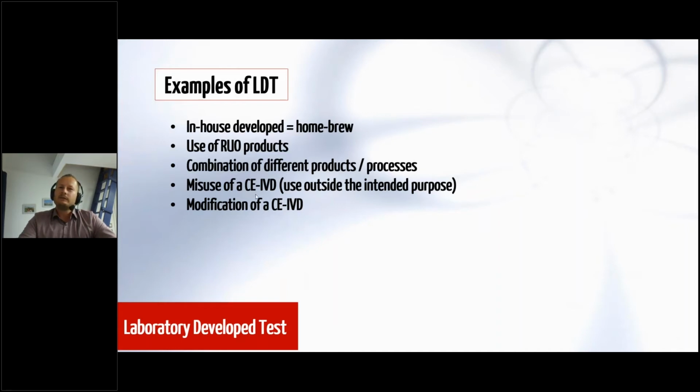A misuse of a CE IVD, so if you use the product outside of the intended purpose or outside of the instructions for use of a manufacturer, it would be a laboratory developed test, and as well if you modify the CE IVD product.